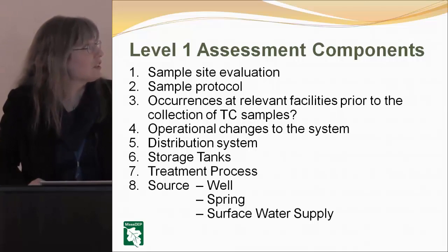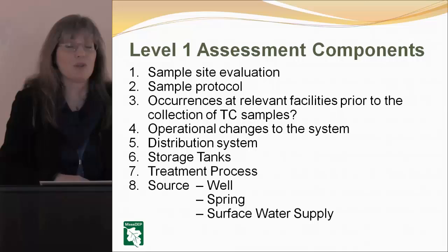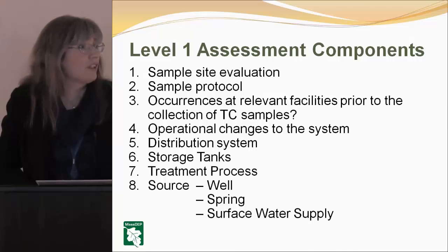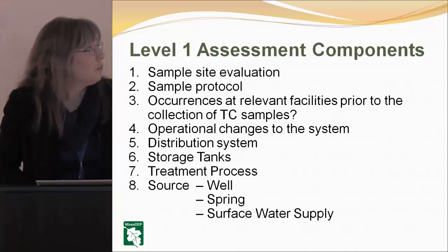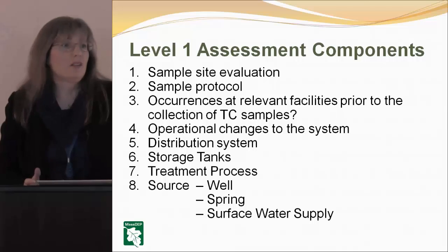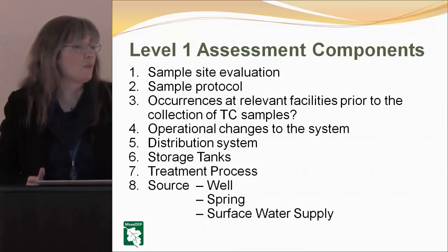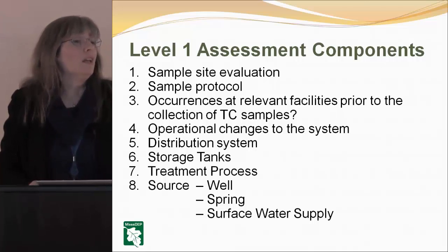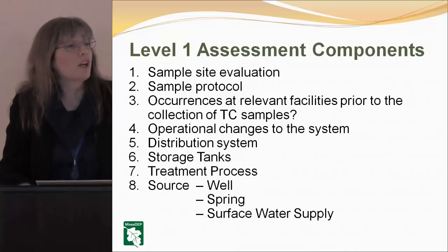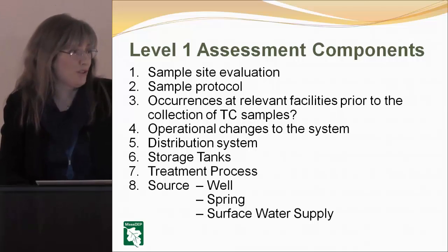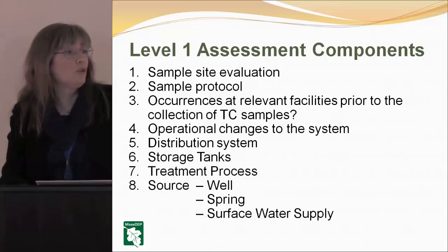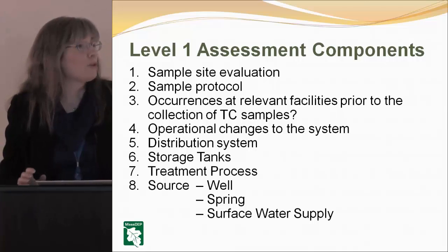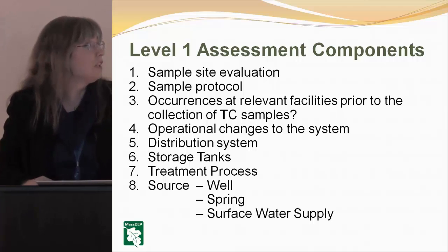Occurrences at relevant facilities prior to the collection of TC samples. If this is a location that you've had problems in the past, has a cross-connection survey been done? Is there something else going on? Is it hooked up to the heating system? Are things not hooked up the way they should be? Has a plumber come in? Maybe you're the public water supplier and you lease it. You lease to someone else and they had someone come in and do some plumbing that you didn't even know about. Have there been changes to the system that you might not have been aware of?